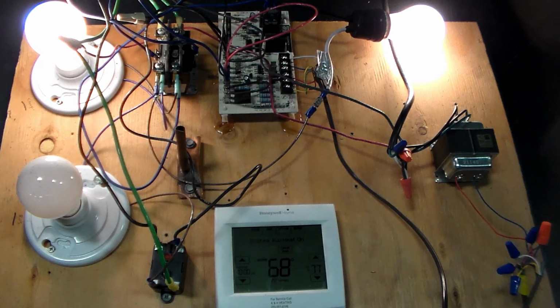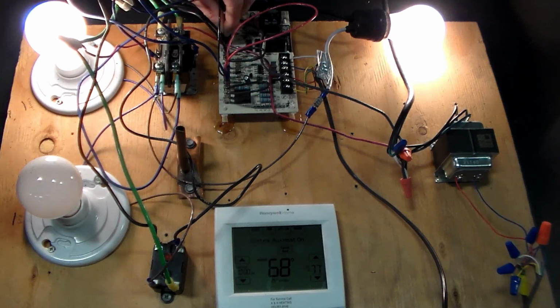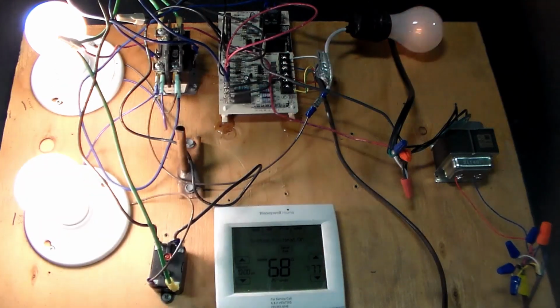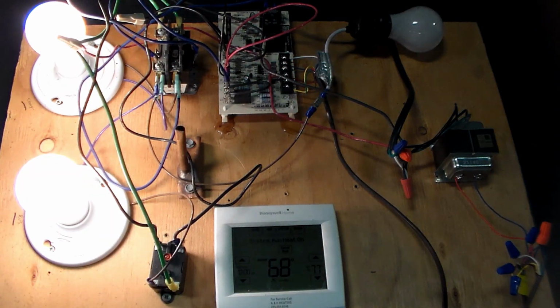Now keep in mind, most boards do this. They're only going to go into defrost for a second or two. There are some out there that'll stay in defrost until you reset them. But a lot of them just go, because when we're testing defrost, what we're doing is just testing, will the board go into defrost? Basically, we're trying to make a determination as to if the board is good or not. If I jump this out to test mode and nothing happens, then I know I have a problem with my board. Right?